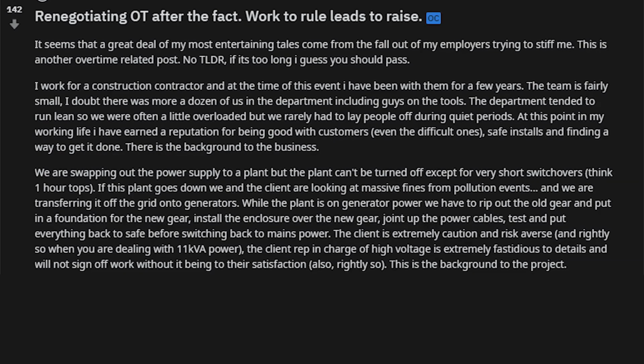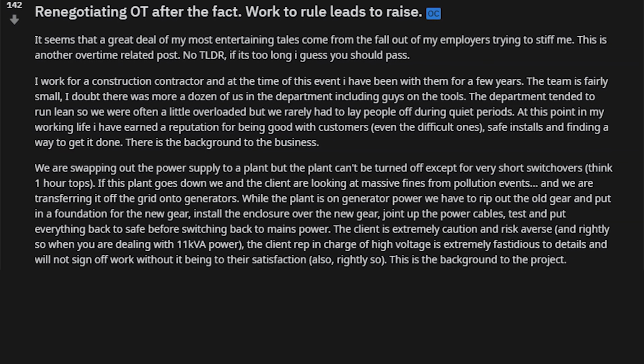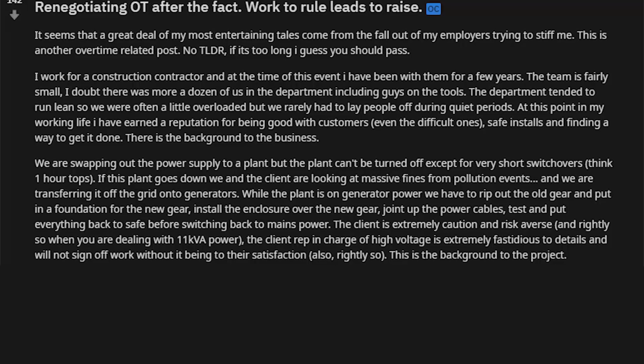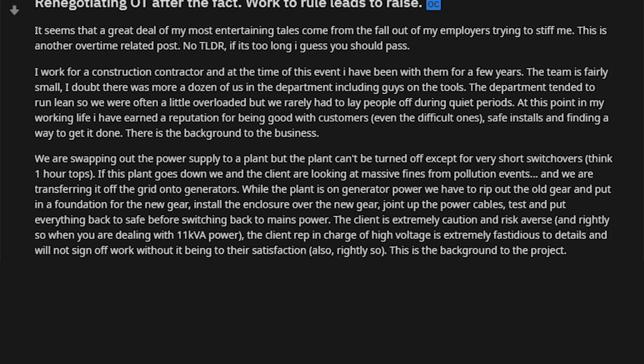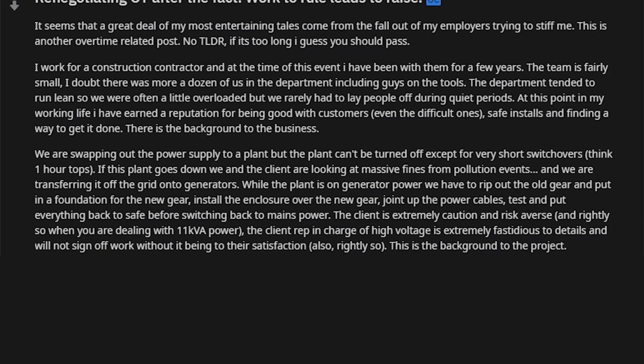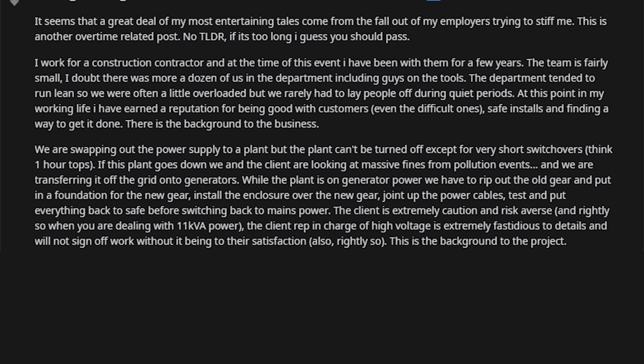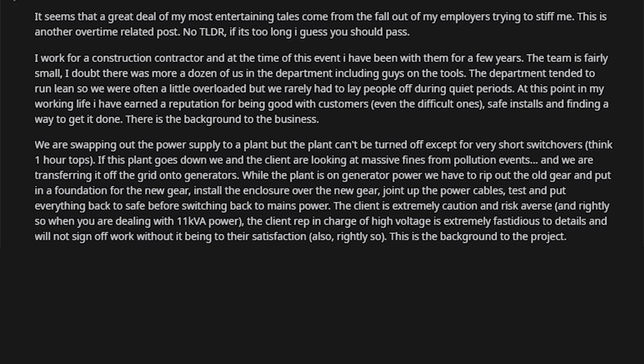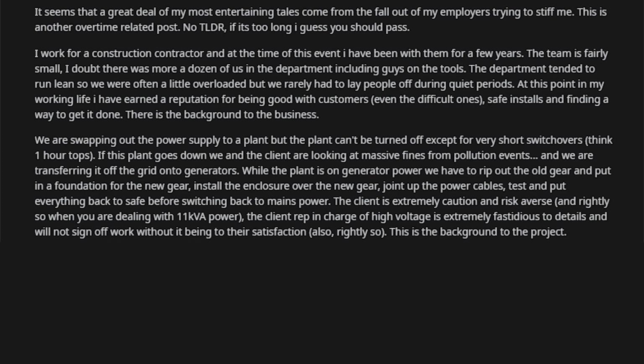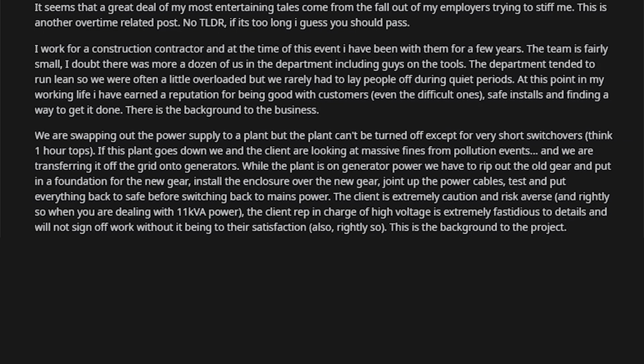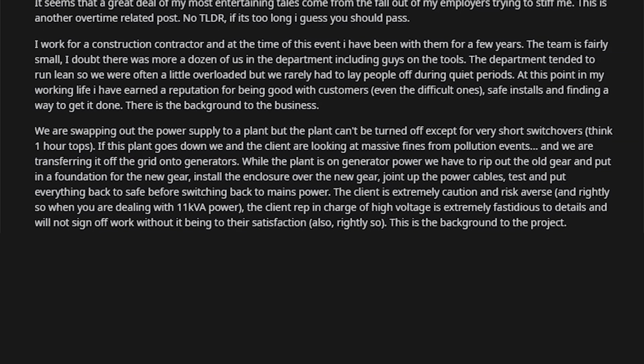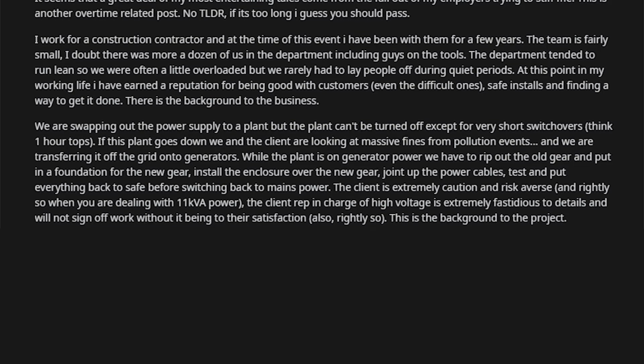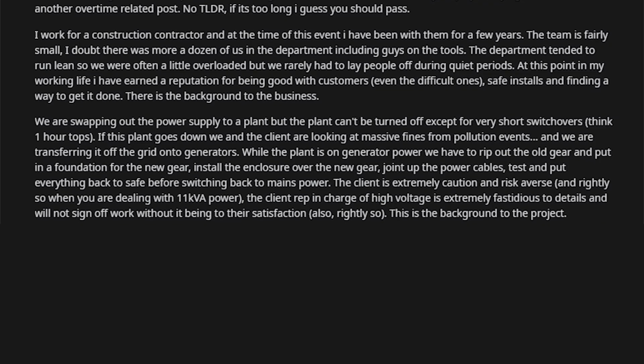We're swapping out the power supply to a plant, but the plant can't be turned off except for very short switchovers, think one hour tops. If this plant goes down, we and the client are looking at massive fines from pollution events, so we're transferring it off the grid onto generators. While the plant is on generator power, we have to rip out the old gear, put in a foundation for the new gear, install the enclosure over the new gear, joint up the power cables, test, and put everything back to safe before switching back to mains power.